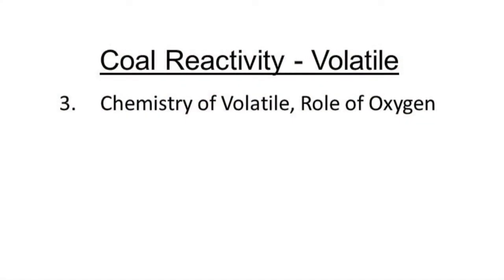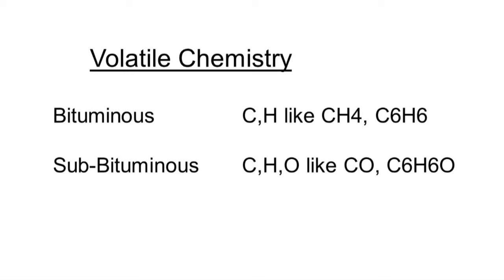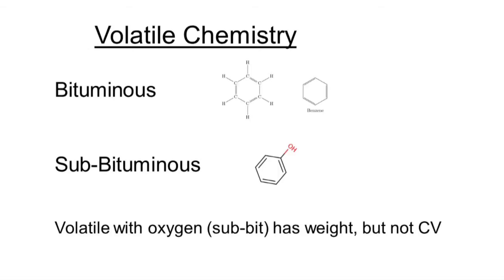A very high rank bituminous or anthracite-type coal, when we look at the chemistry of the volatile matter, is mostly hydrogen and carbon — a hydrocarbon with very little oxygen involved. But if we look at the volatile matter of a sub-bituminous or lignite coal, we'll see things like carbon monoxide in the volatile matter, or phenols versus benzene in the aromatic rings — we'll actually see a more oxygenated volatile matter. This oxygen content in the volatile matter adds to the weight of the volatile but doesn't necessarily add calorific value to it.